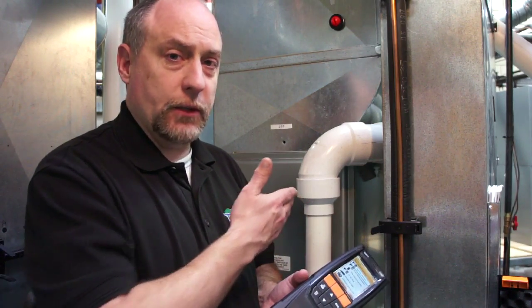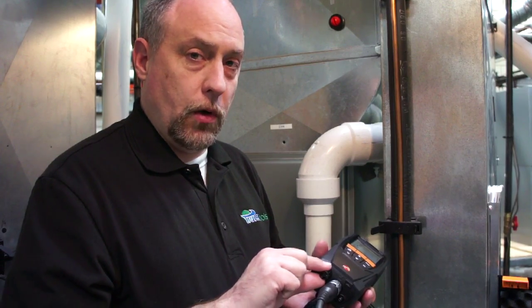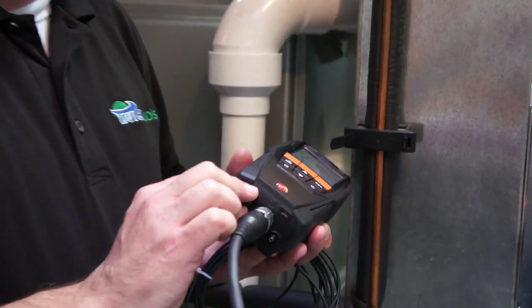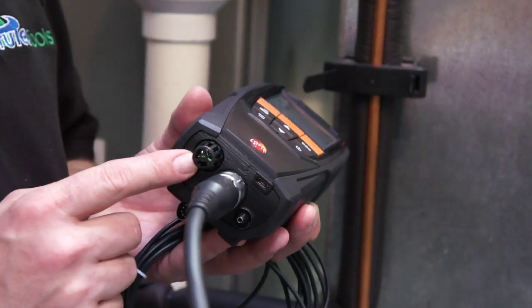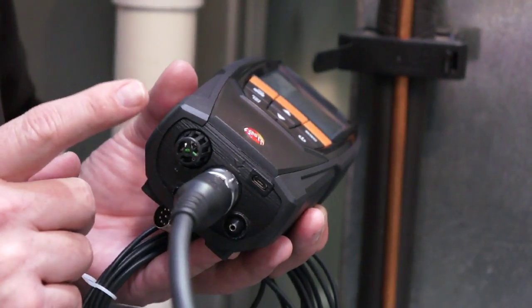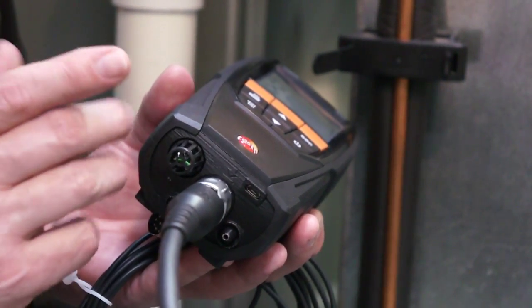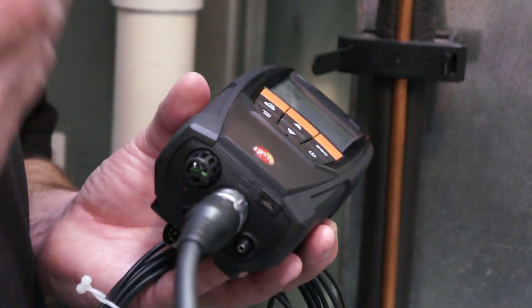Most atmospheric appliances get the air for combustion from the basement. In this case, we have a 2-pipe 90 plus and we're getting air from outdoors. So in order to get an accurate efficiency reading, we actually have to get the outdoor air temperature, because what we want to measure is called the net stack temperature, which is simply the gross stack temperature minus the combustion air inlet temperature. So what we're going to do is pull the thermistor out of the bottom of the instrument, and this thermistor comes standard in the 320, and is simply used to measure the combustion air temperature or the room air temperature that we'd typically be working in.